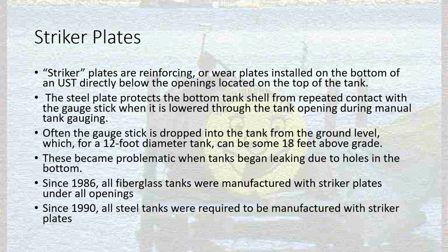They would bounce the stick off the bottom and try and see how high they could get it to go to catch it. And inadvertently, they would stab holes in the bottom of these tanks. So it became a known problem over time. And so they started putting in the UL standards that you had to have striker plates beneath the openings so that would prevent them from poking holes in the tanks whenever they're lowering inventory or manual stick gauging is going on.